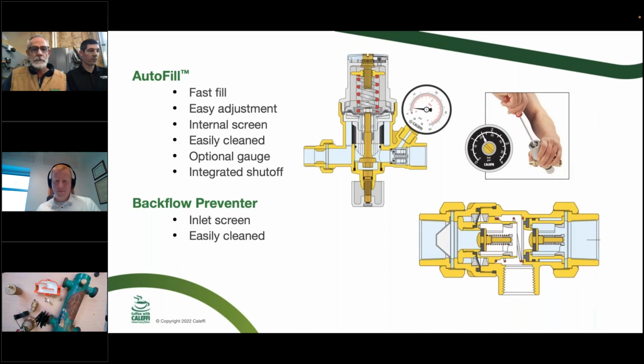So for the AutoFill, here are a couple cutaways. Cody, do you want to kind of narrate what happens inside of these devices? Yeah, so, to bring this full circle, anytime you have air removal or dirt removal in a system, you're blowing down dirt and debris, you're going to have something to make up that volume of air or that volume of fluid that got blown down from the dirt separator. And that can be done with an automatic type fill valve like our AutoFill.